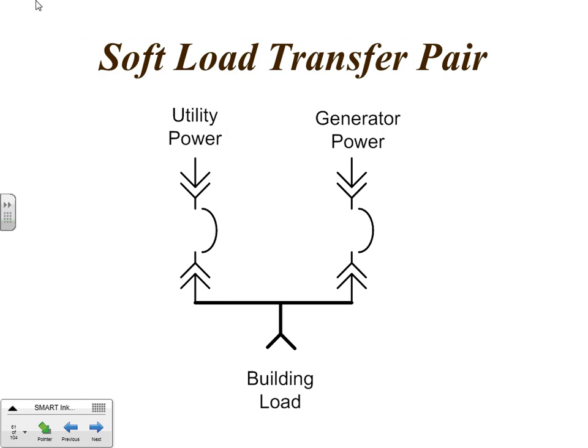The building load down here, this can stay closed for a long period of time. Typically, it stays closed for a few seconds rather than a transfer switch. A closed transition switch is closed only for 100 milliseconds. This could stay closed for several seconds. So what happens is the power fails out here. This is a failure, and the generator set will come up to speed and frequency and close its breaker to this load. Before the generator starts, it also kicks this breaker open, so the utility cannot come back and knock the generator out of phase. So that's the first thing that happens in the power failure.